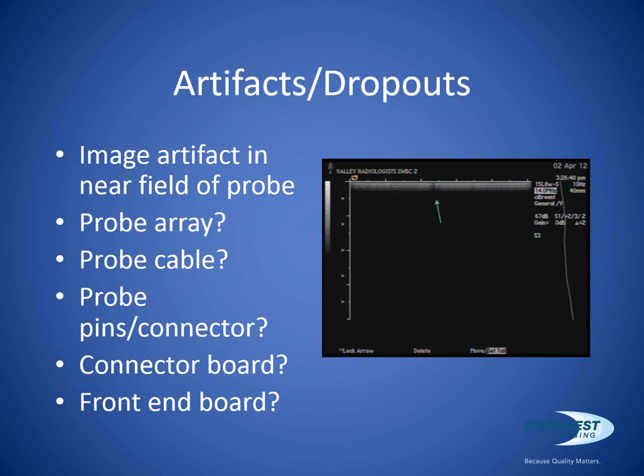And then we want to look at front-end boards. So if we've isolated the probe, okay, the array is fine, the cable is fine, we've tried a different probe, we still have this artifact. At that point, we have to start looking at the machine. Is it within the front end of the machine? And what I have here is various block diagrams for front ends of the systems, and we're not doing system training today, so I'm not going to spend too much time on this. But you can see from this is the Acuson Sequoia. Not a lot of Sequoias out there still, but I'm sure there are some at some of your sites.